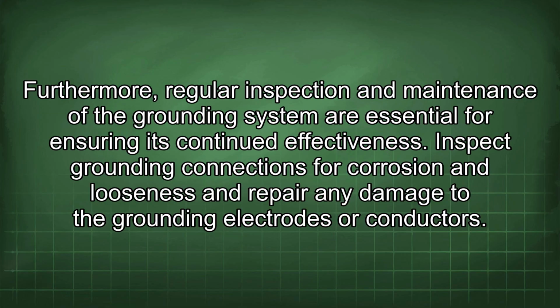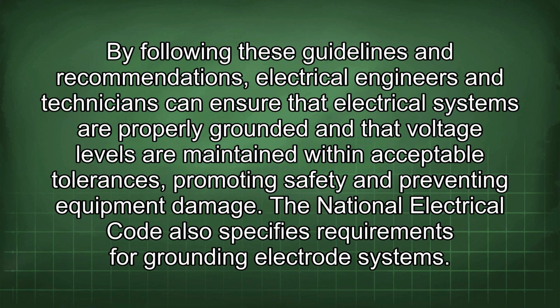Furthermore, regular inspection and maintenance of the grounding system are essential for ensuring its continued effectiveness. Inspect grounding connections for corrosion and looseness and repair any damage to the grounding electrodes or conductors. By following these guidelines and recommendations, electrical engineers and technicians can ensure that electrical systems are properly grounded and that voltage levels are maintained within acceptable tolerances, promoting safety and preventing equipment damage.